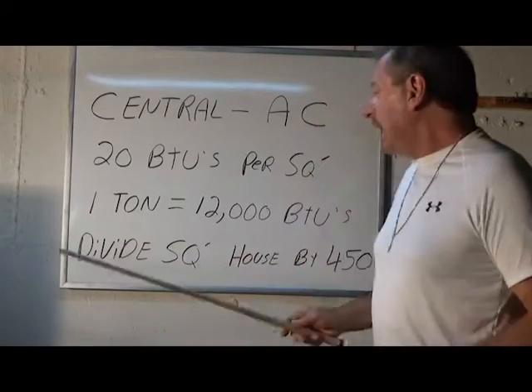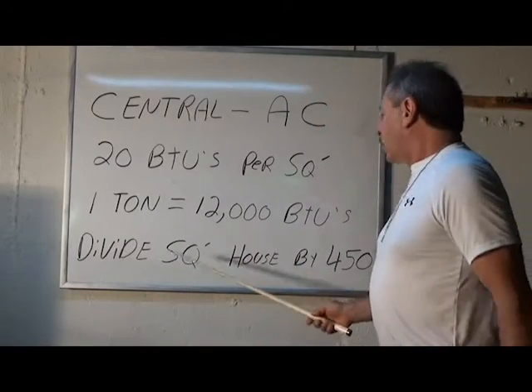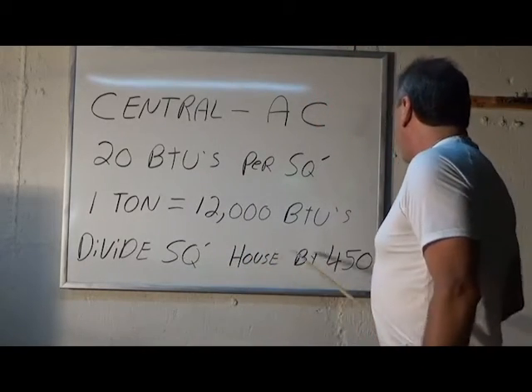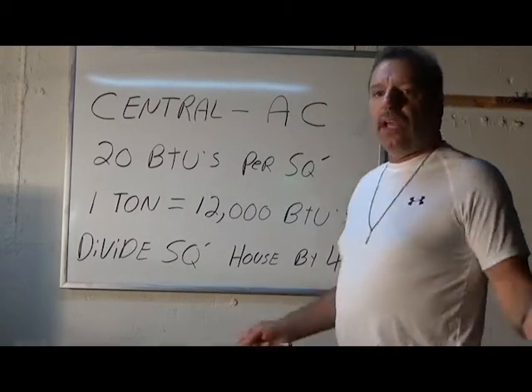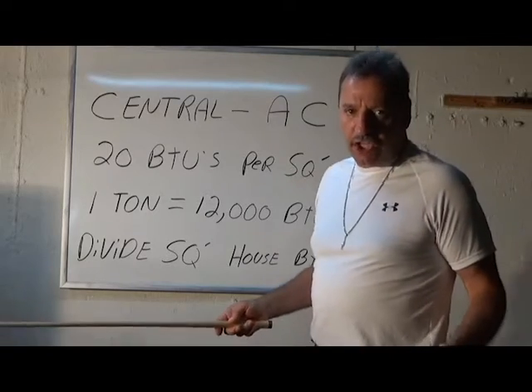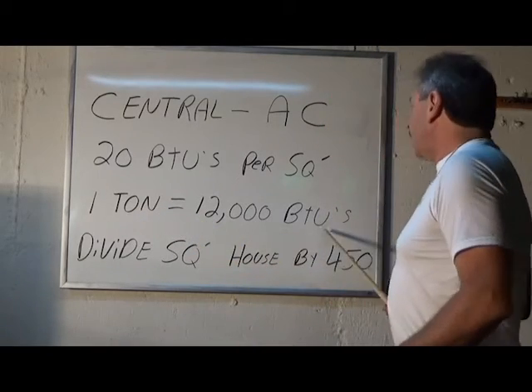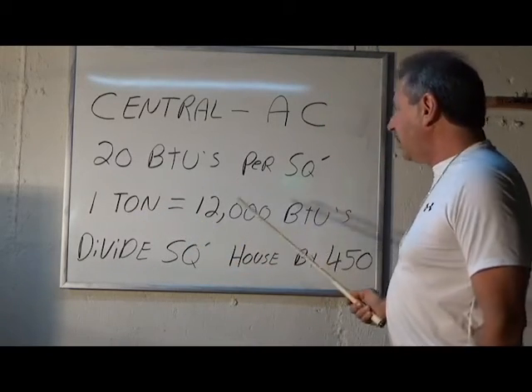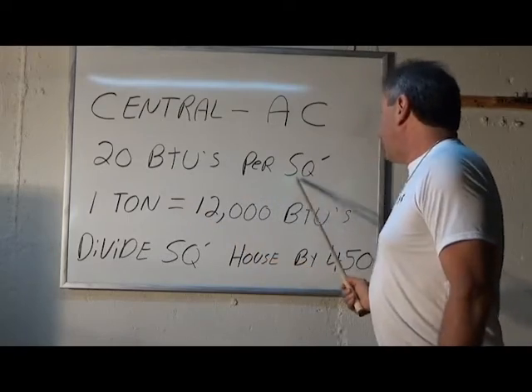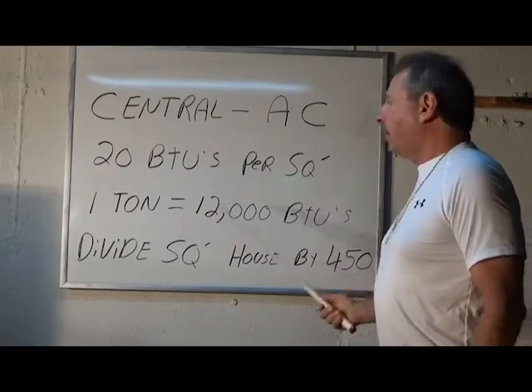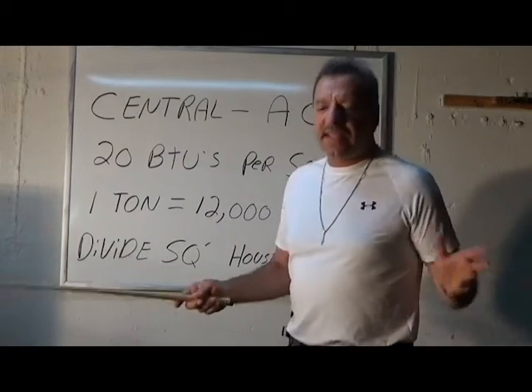Any square footage of the house divided by 450 will give you the tonnage. 1 ton equals 12,000 BTUs. You need 20 BTUs per square foot. That's the rule of thumb.